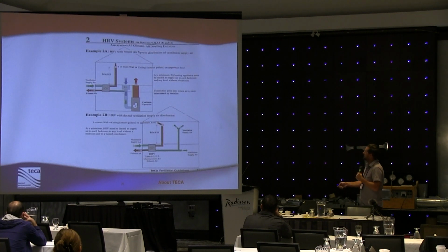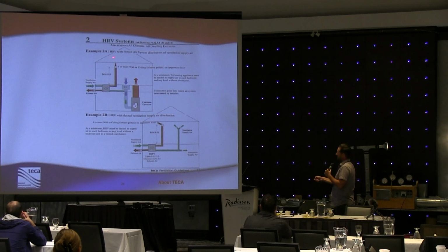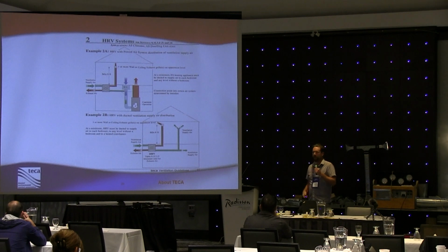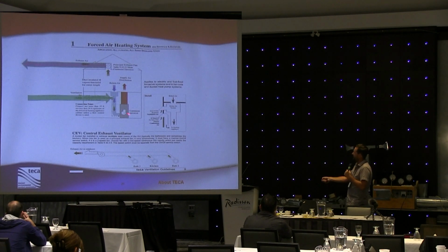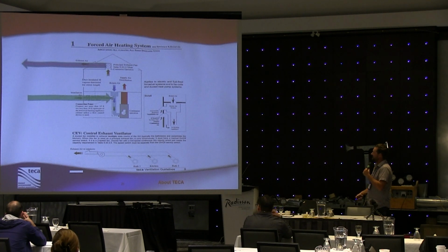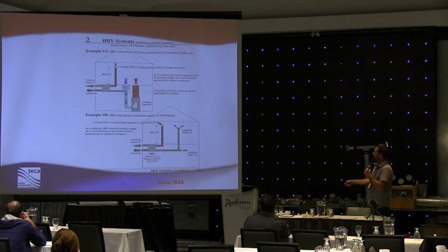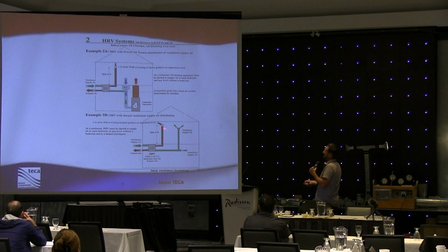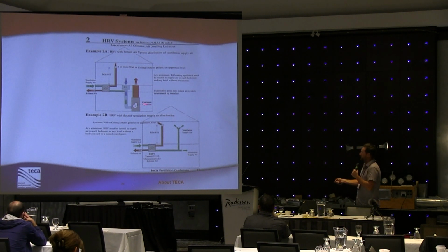Here's a little look at our HRV systems. The HRV systems, again, right out of the building code, it talks about the HRV system and how this is set up. Well, there's two options here. We've got our example 2A, which is an HRV system set up with a forced air. So you can see, very similar system here. We've got a furnace. We've got this supply trunk coming off the top, or the supply air. This is the air that's been conditioned, that's going to be distributed throughout the building. There's our return air. Same thing goes with the HRV. We've got a furnace, we've got a return air, and we've got a supply air that is distributing the airflow throughout the building. Again, the furnace blower motor must be set to run continuously on a low speed.